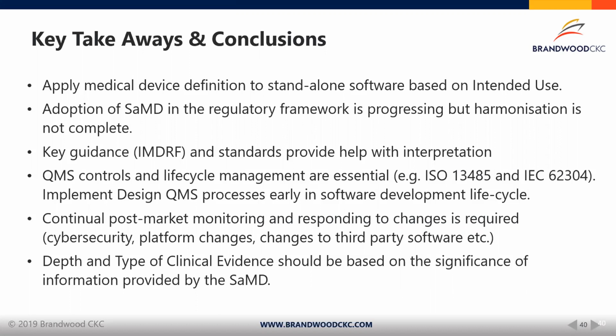The adoption of software as medical device in the regulatory framework is progressing. We presented some integration within the MDR. There are a number of guidance documents published by other regulators around the integration of software as standalone medical devices in the regulatory framework, but this harmonization is still not complete, and there are still some differences. Key guidance documents: we've presented 4 guidance documents that look at key elements of definitions, risk management, quality management system, and clinical evidence, to help with interpretation and with the transition to new regulatory models. And we strongly encourage you to consult the IMDRF document if you're involved in software development, to make sure that all considerations and regulatory interpretations are taken into consideration.